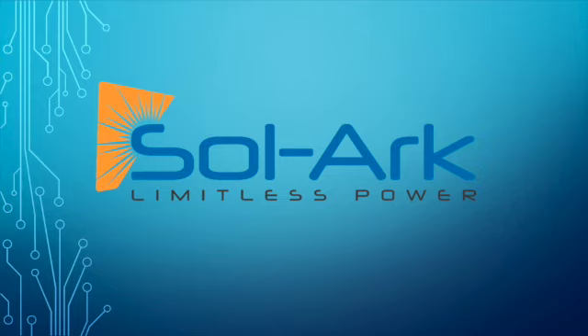Thanks, Tom. Wish we had a 4 or 5K Sol-Ark to offer. We don't do small inverters. We did in the past, and people just overloaded the heck out of them, and that leads to so many problems. So everybody is pushing us to do bigger inverters, not smaller ones. The smaller the inverters you go, the more support you need because they're overloading the inverter much more often. So I'm really not a fan of smaller inverters like 4 or 5K. There are some other options out there, like Schneider has a good solution at 4K. And for 5K, I think, let's see, Outback, which one was it? The Skybox. There's a couple other lower cost solutions for 4 and 5K from those two companies I just mentioned.